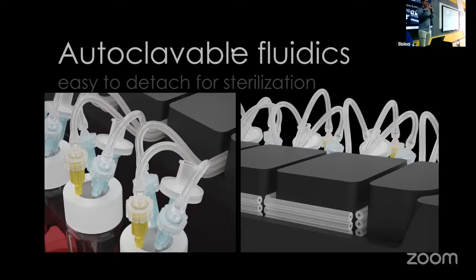Very good. These methods are necessary to make sure that everything is sterile and only our bacteria of interest are growing. And in the case of Replifactory, the very nice thing about it is that the fluidics is easy to autoclave. So you can remove it as a closed system, just put it in the autoclave where it's heated up to 121 degrees, and the steam at this temperature and high pressure kills off every living organism.